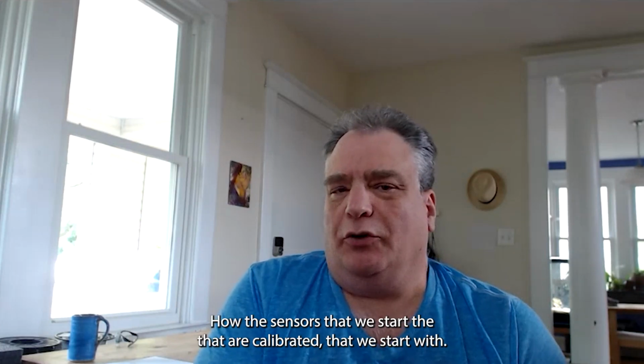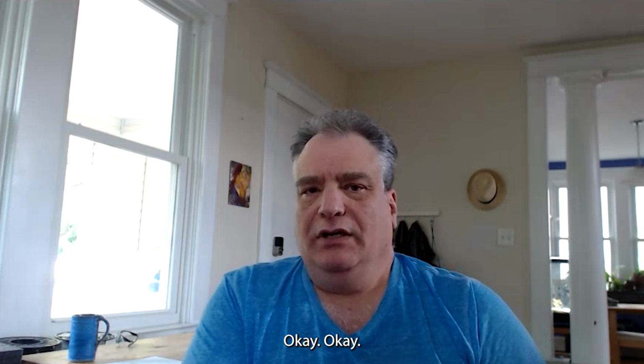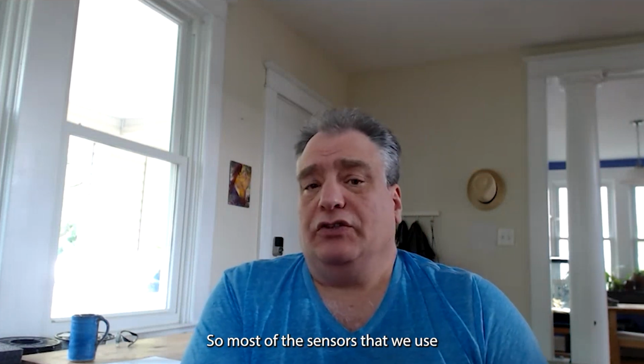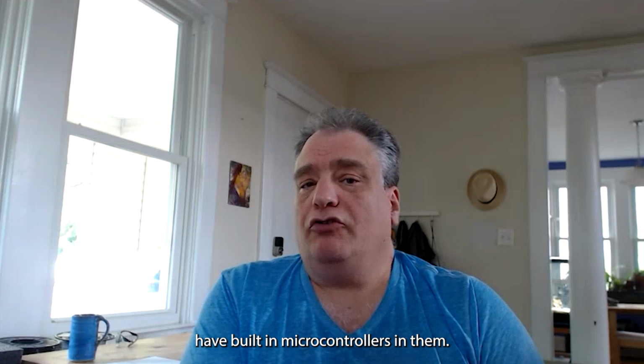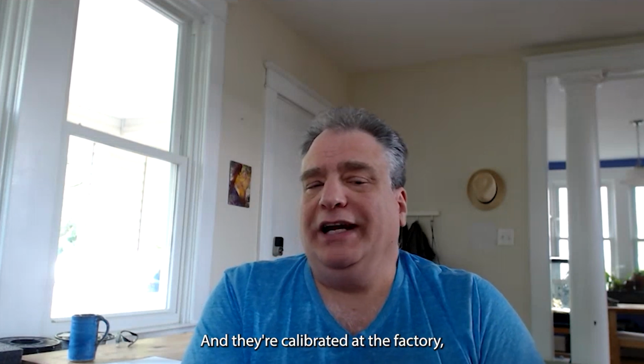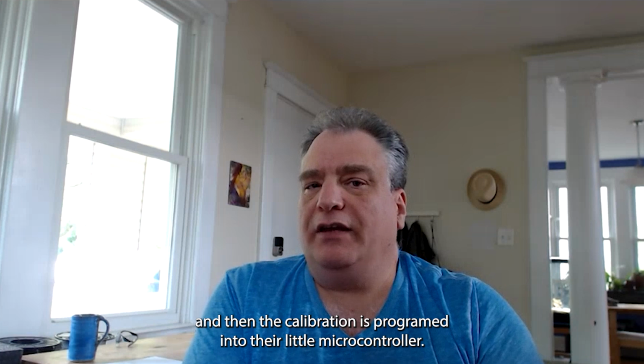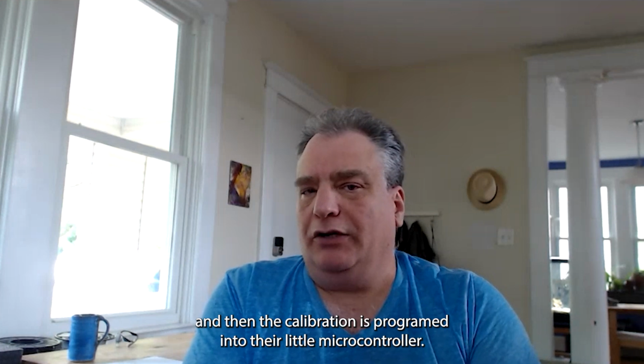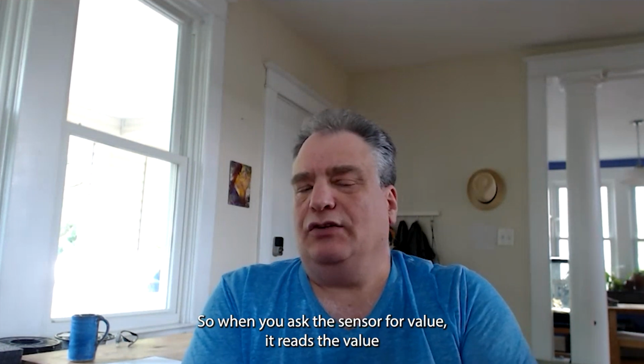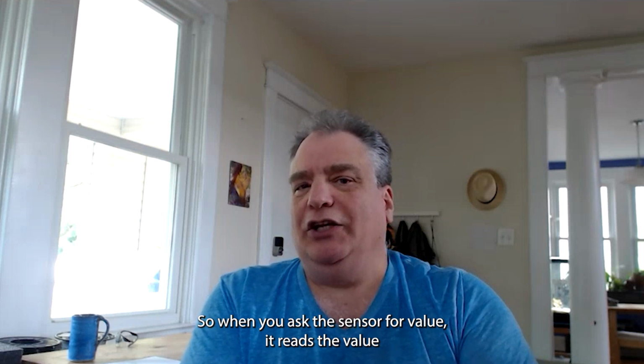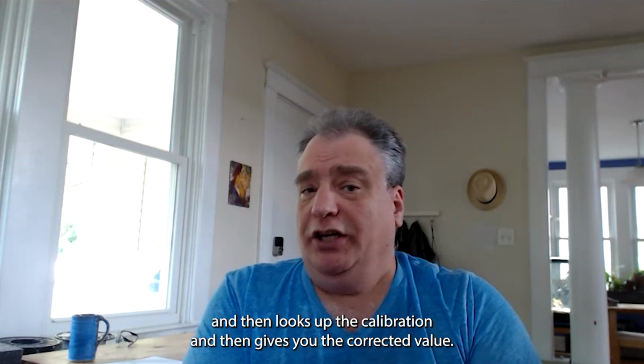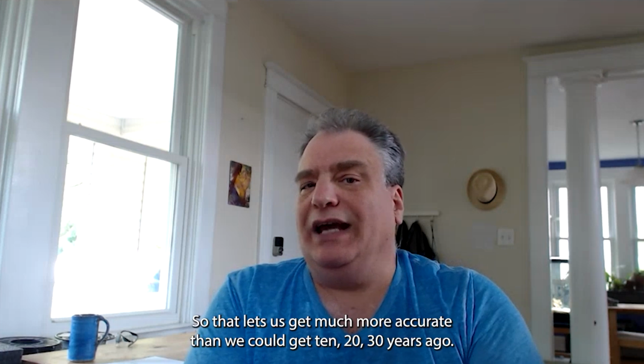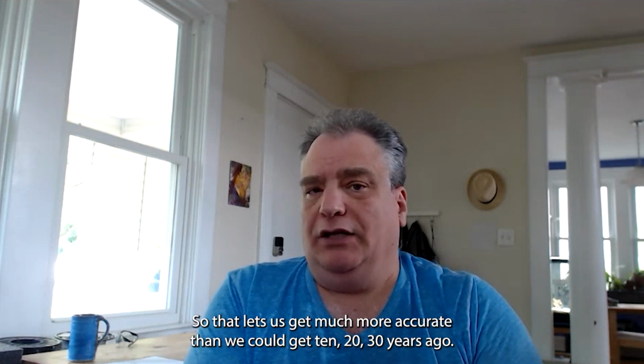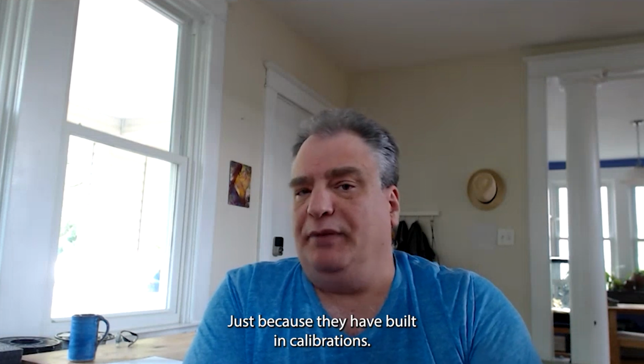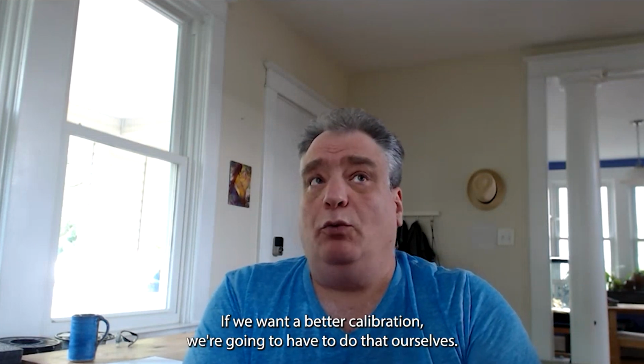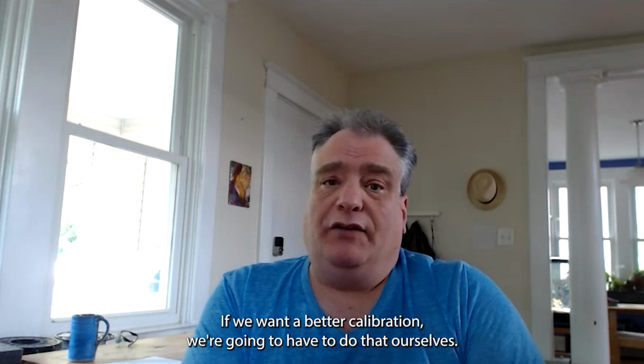How are the sensors calibrated that we start with? Most of the sensors that we use have built-in microcontrollers in them, and they're calibrated at the factory, and then the calibration is programmed into their little microcontroller. So when you ask the sensor for a value, it reads the value and then looks up the calibration and then gives you the corrected value. So that lets us get much more accurate than we could get 10, 20, 30 years ago, just because they have built-in calibrations. If we want a better calibration, we're going to have to do that ourselves.